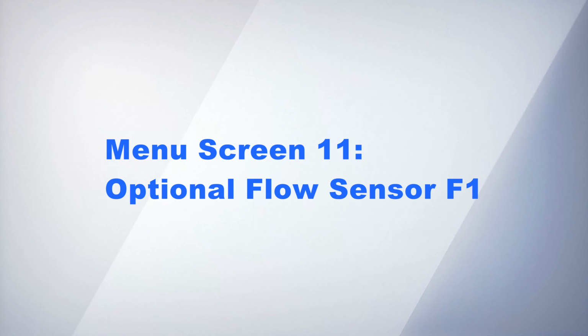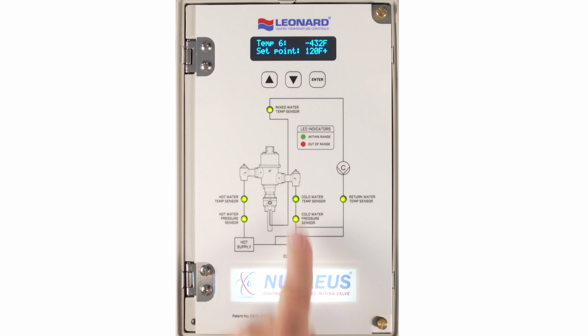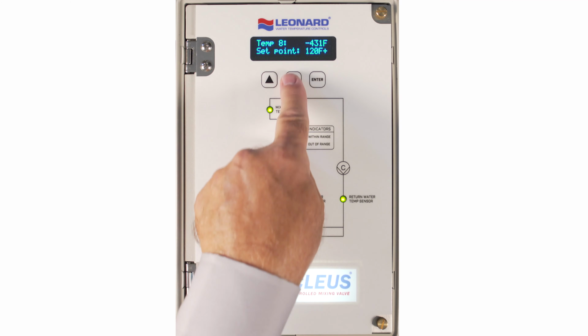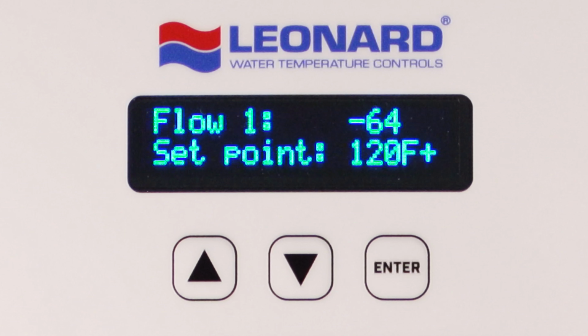Menu screen 11. Optional flow sensor, F1. Pressing down 11 times displays flow 1. This indicates and displays actual flow in GPM on flow channel 1 for the optional daughter board. See O&M manual for wiring setup. Note: a large negative value displayed at the flow 1 line is an indication that there is no sensor installed to the main control board, or the wiring to the main board is improper, or the sensor is damaged.